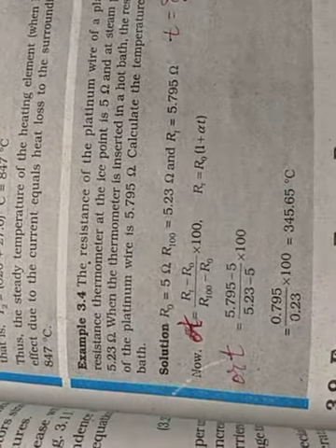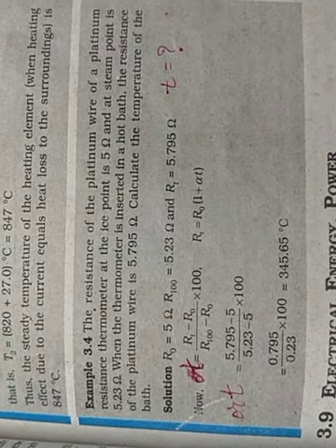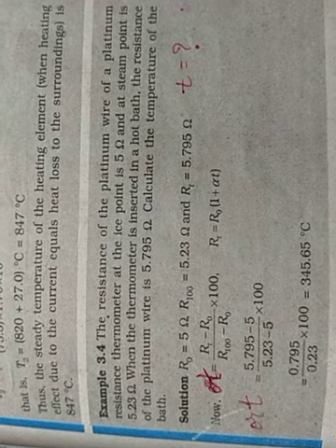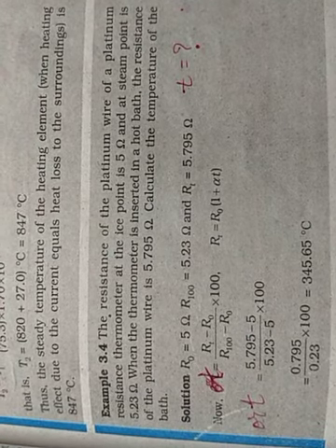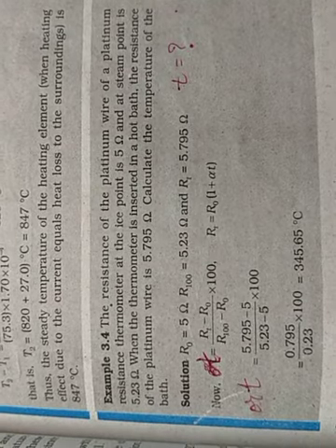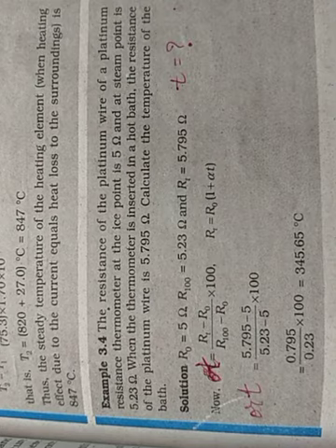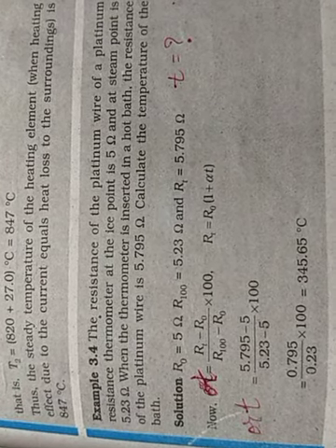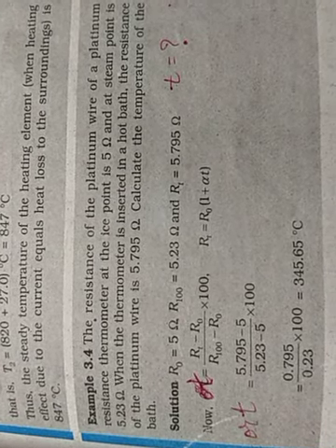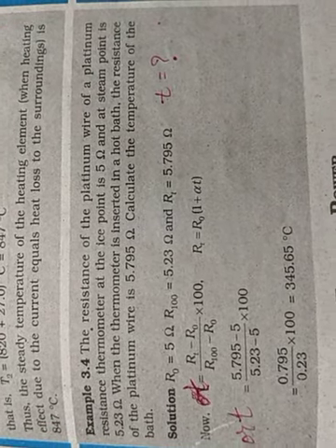Now we again have another example. The resistance of the platinum wire of a platinum resistance thermometer at the ice point is 5 ohm and at the steam point is 5.23 ohm. When the thermometer is inserted in a hot bath, the resistance of the platinum wire is 5.795 ohm. We have to calculate the temperature of the hot bath.